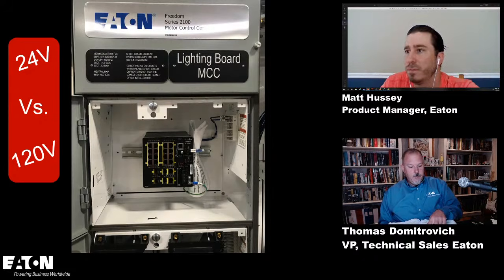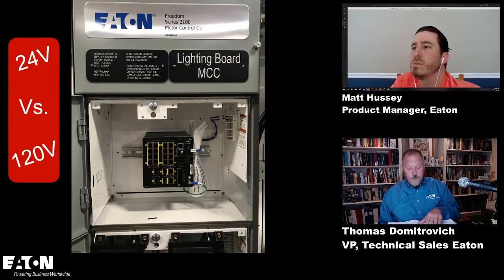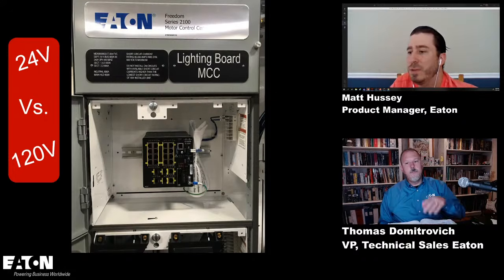But as I read D, it talks about a quarter inch between non-power limited fire alarm and medium power network broadband communication circuit conductors, routed to maintain a minimum of a quarter inch separation from the conductors and cables of Class 2 and Class 3 circuits. So in our construction, we would have to maintain that quarter inch when we put it together as part of an assembly, right? It's integral to the assembly, so recognize that is the installation cabling we're talking about. Our cables are tested and listed within our assembly. Good point, so it's part of the listing.